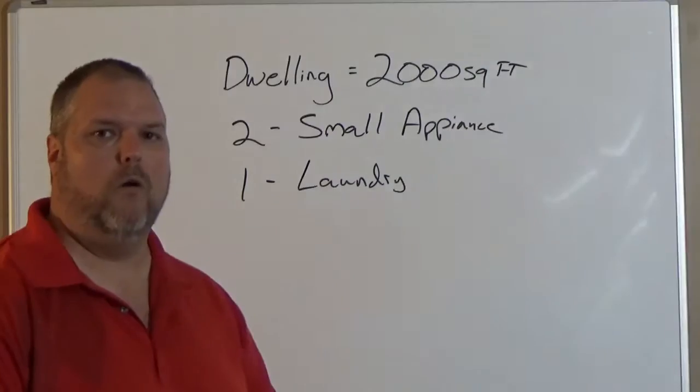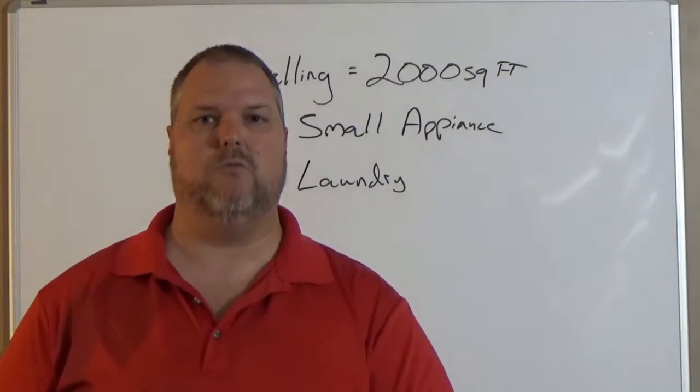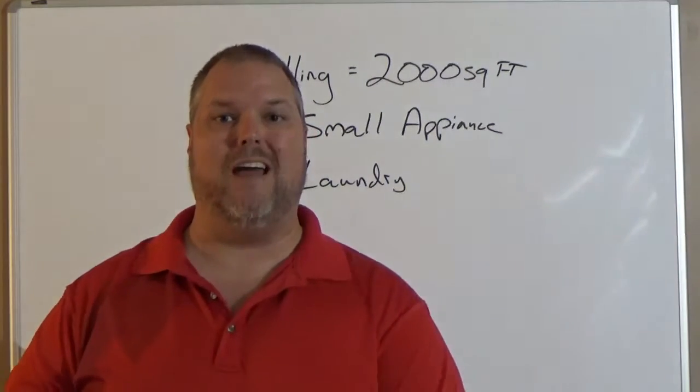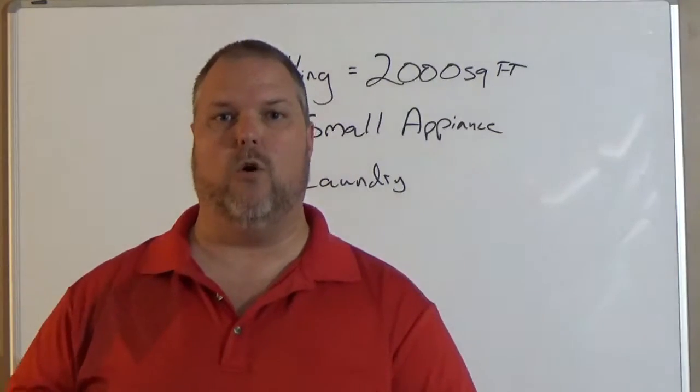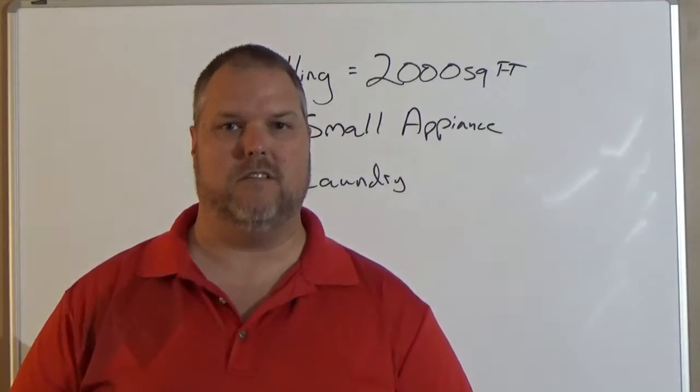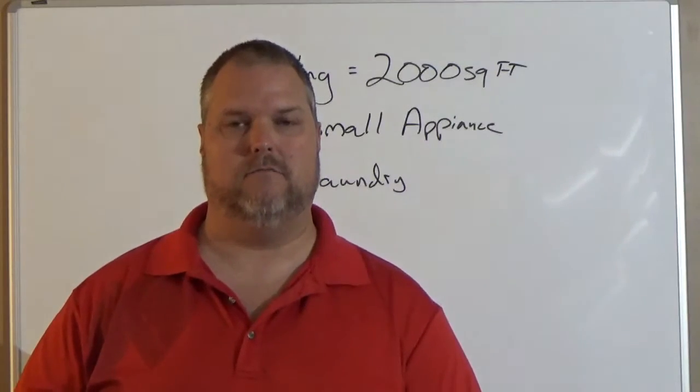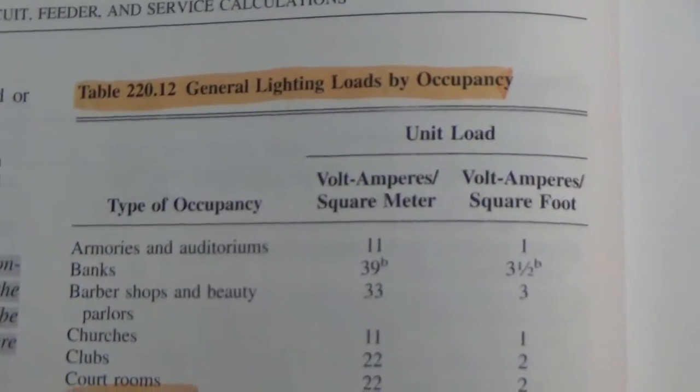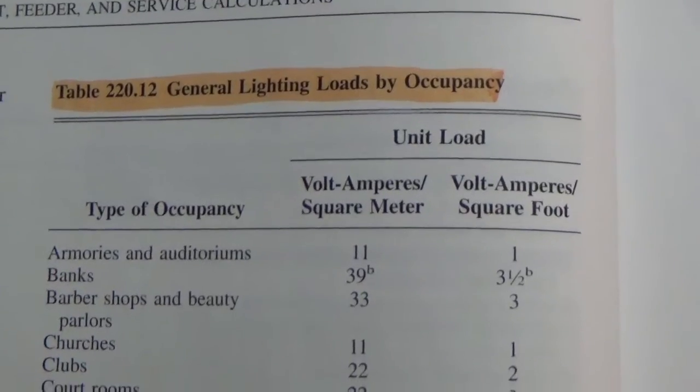Our dwelling is 2,000 square feet. We have two small appliance circuits and we have one laundry circuit. This is all you need to size the general lighting load. I have to take the square footage and break it down into a VA, or a wattage. VA stands for volt amps. Volt amps is the same as watts. How do we find VA? Come over to the code book and we look at Table 220.12, General Lighting Loads for Occupancy.